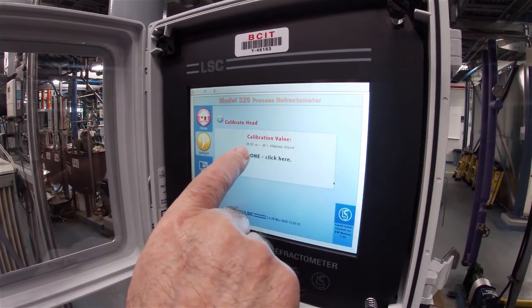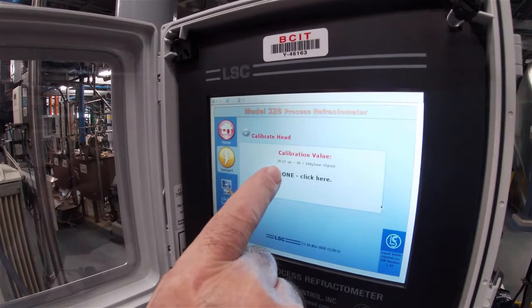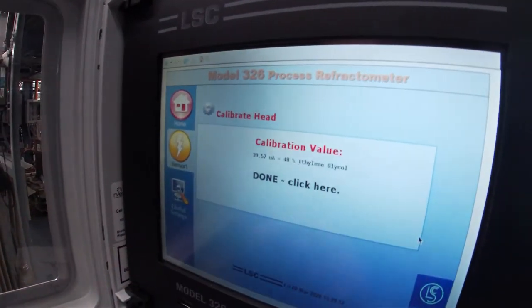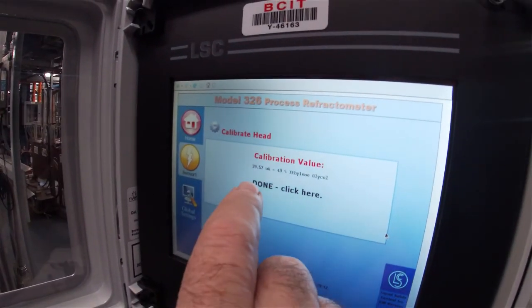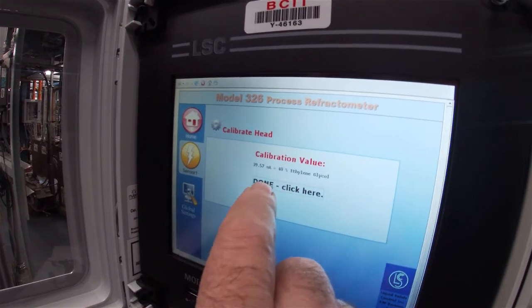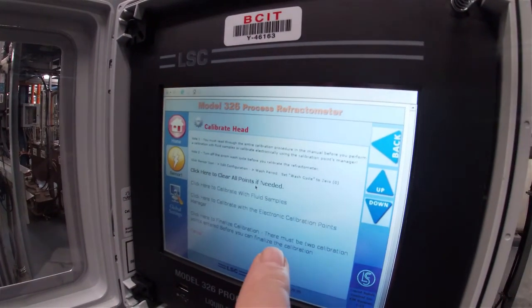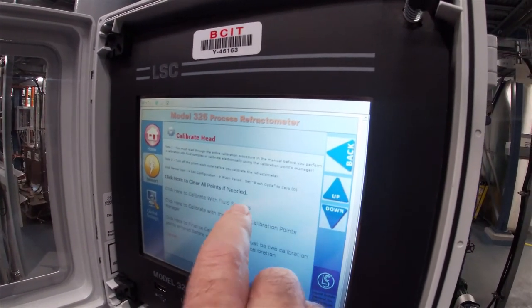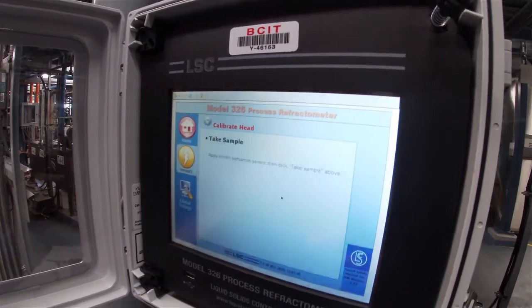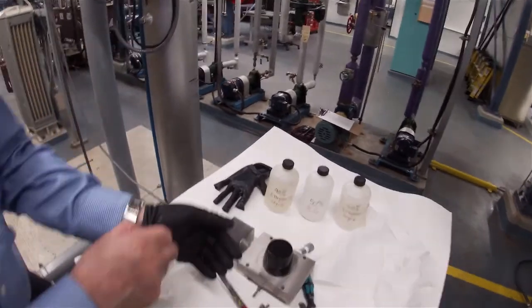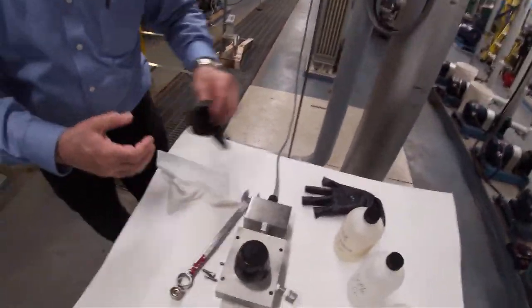And when we're done, that's the microamps that are coming from the sensor, and you can see that it now knows that that's 40% glycol. So it's done, click here. And back to calibrate with samples. Now we're going to take this sample off. And I'm going to get rid of this other glove.